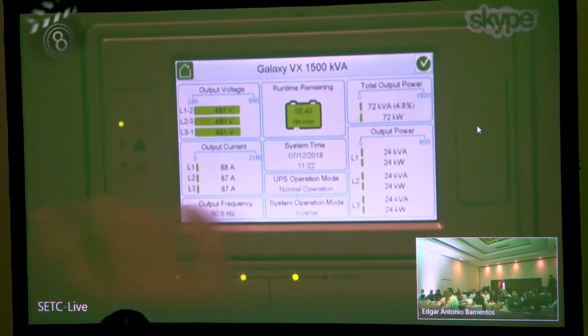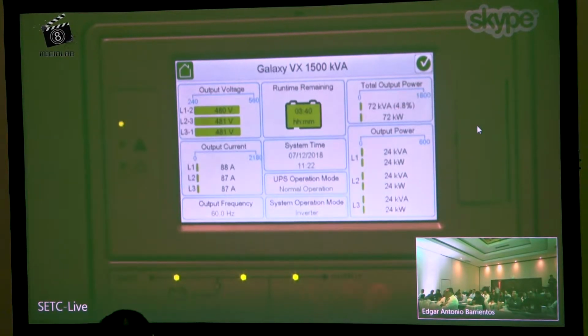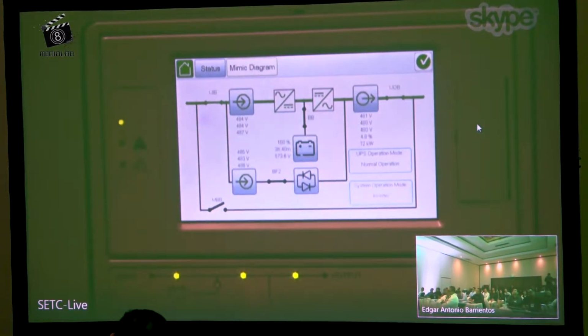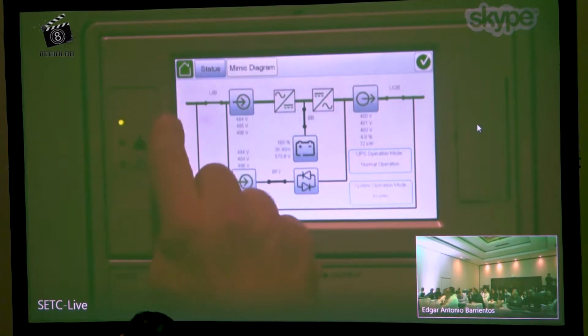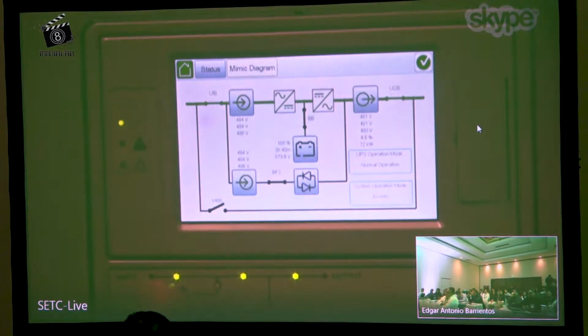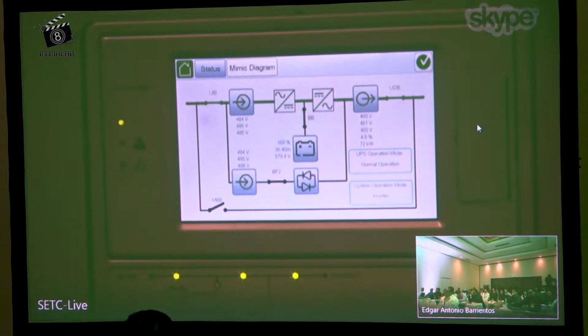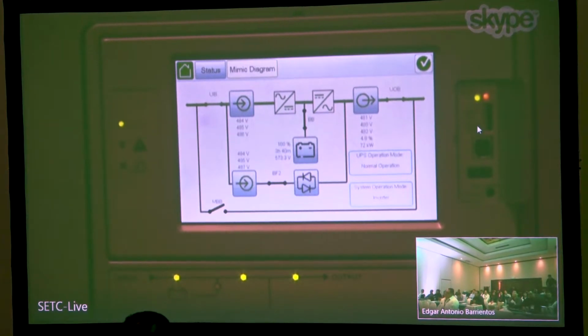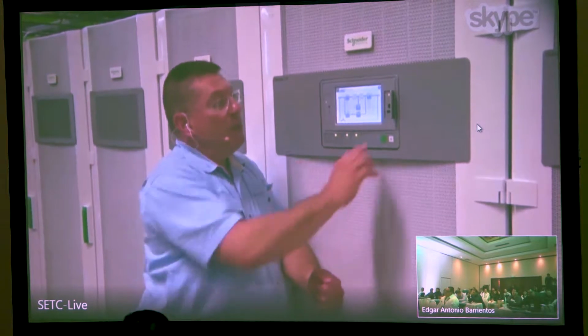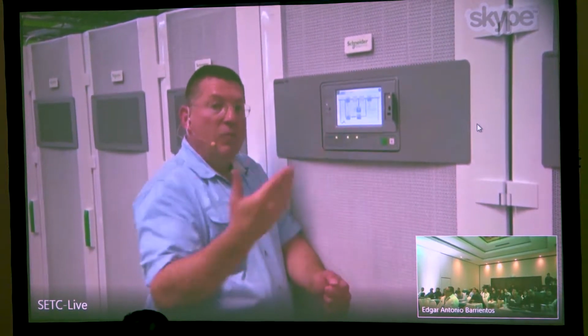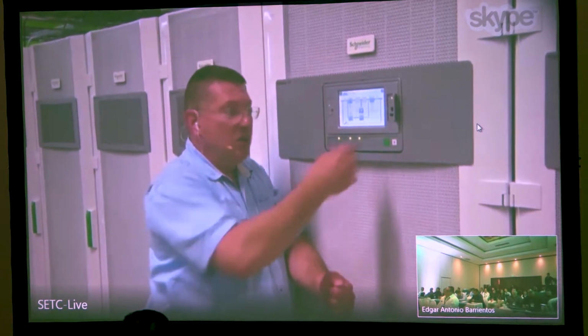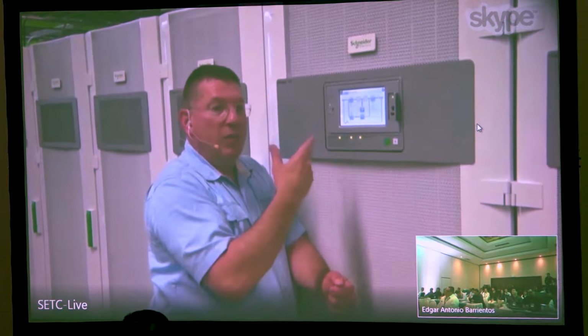So what I want to show you is we're going to work with the GUI here, but we have two interfaces, as I mentioned. I want to show you the mimic bus. I like this. This gives me a good power flow. So we have the mimic bus here, shows power coming in through the rectifier, charging the batteries, inverter and out, the bypass. Then we have this LED interface here with a push button static bypass inverter button. The little door behind this is where field service engineers would connect with their computer and the tuner. Then there's also a USB port here where you, as the end user, could actually come up and go to the screen for logs.